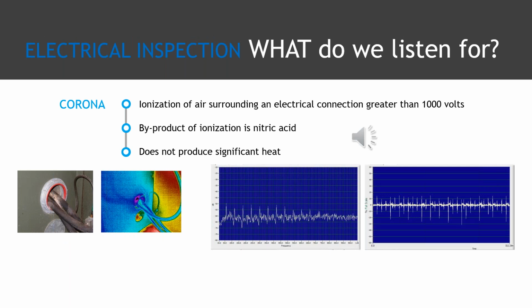So what's corona? If we're listening for corona, typically we get a lot of corona on insulators outside in a substation. We don't usually hear a lot of corona internally in switchgear. Most of what we hear in switchgear is going to be a little more escalated than that, tracking. But if you have a substation at your facility, it's a good idea. Ultrasound gives you the advantage of being able to stand outside the fence and scan from a pretty good distance and listen for things like corona. It's not always damaging right away, but it certainly can lead to other more severe problems.